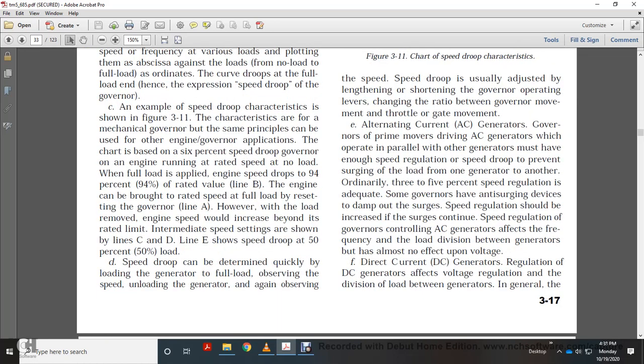An example of speed droop characteristics: for a 2,300 RPM engine with a mechanical governor, the chart is based on 6% speed droop. When full load is applied, engine speed drops to 94% of rated value. The engine can be brought to rated speed at full load by resetting the governor in Line A; however, when load is removed, engine speed would increase beyond rated limits. Intermediate speed settings are shown in Lines C, D, and E, illustrating speed drop at 50% load.